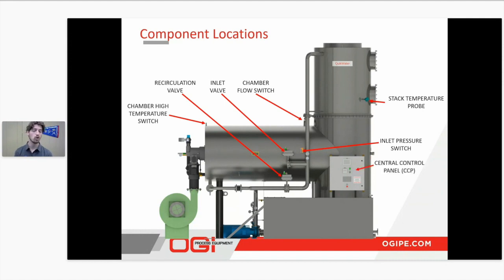Our central control panel, where our HMI and emergency stop button will be located on each unit. And lastly, our tank and temperature probes, along with the level floats. So these will be monitoring your call for fill on the QuikWater unit and the recirculation. So once this reaches a certain point, we'll go ahead and cut off that inlet valve. If the water is still not at temperature, we'll go ahead and initiate that recirculation valve, get that water up to temperature in the internal tank, and have it contact your process.